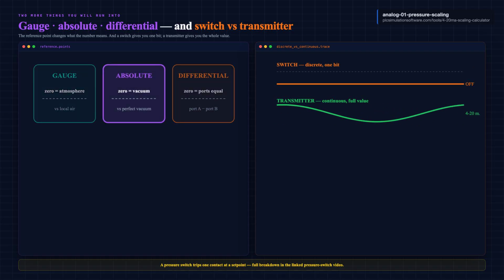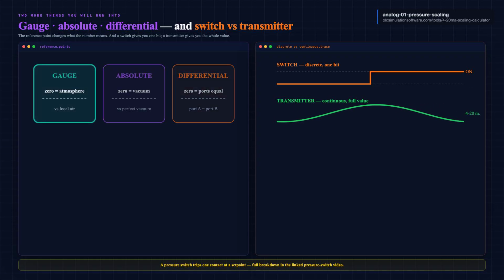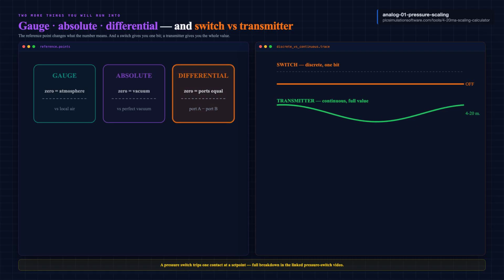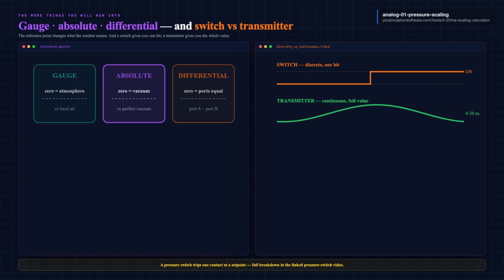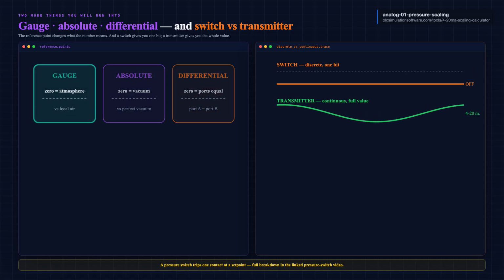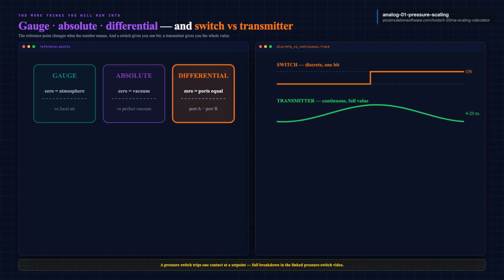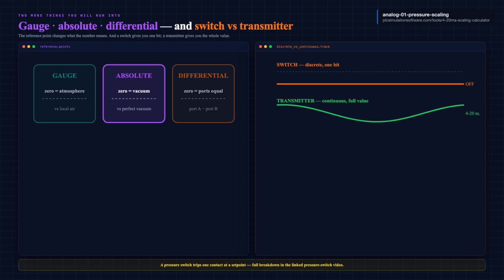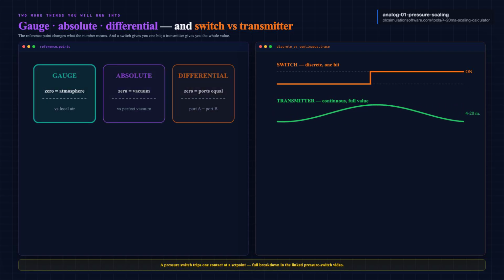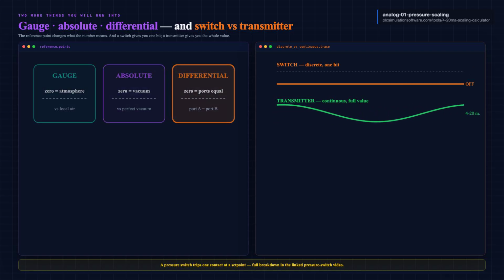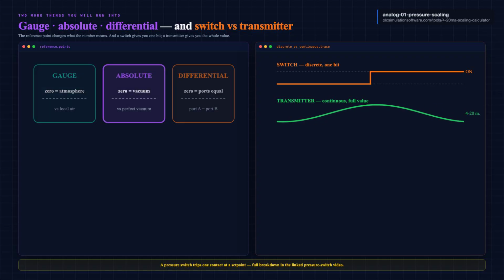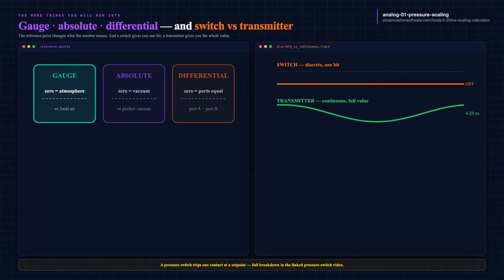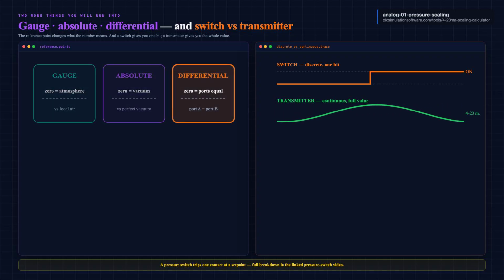Second, switch versus transmitter. A pressure switch is discrete. It trips one contact at a set point, on or off, 1 bit. A transmitter is continuous. It streams the whole measured value all the time. I dig into the switch side in the linked pressure switch video. The point here is simple. A transmitter gives you the full reading, not just above or below a line.